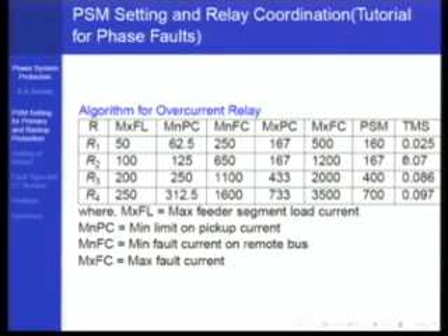Now, how did I get this 0.07? We need to work that out; that is the next step. First we will finish up with the PSM step. Now, relay R3 sees 200 amperes current, so the minimum pickup, which is 1.25 times it, will be 250 amperes, and the minimum fault current on its primary feeder is 1100. But the maximum pickup is not 2/3 of 1100 again.